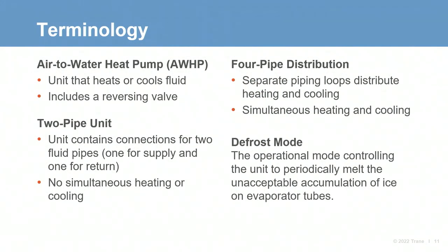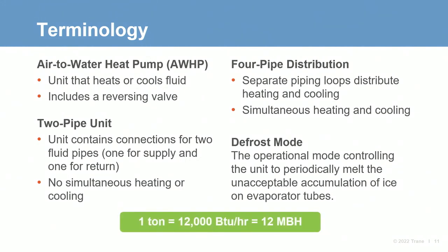In lower ambient climates, air-to-water heat pumps must enter defrost mode to melt ice that's built up on the air-to-refrigerant coil. We'll discuss how that affects plant capacity and unit sizing. And lastly, units of tons are typically used for cooling capacity, but BTU per hour is typically used for heating capacity. Note that 1 ton equals 12,000 BTUs per hour, which is equivalent to 12 MBH. Now, common language here will help us stay on the same page. So, okay, Charlie, help us understand what a chiller heater system is.